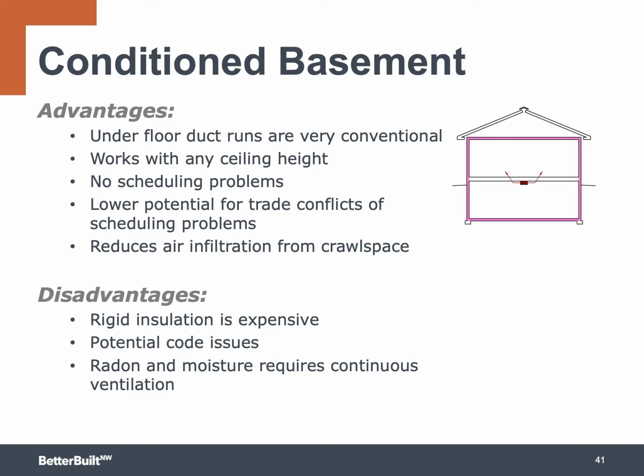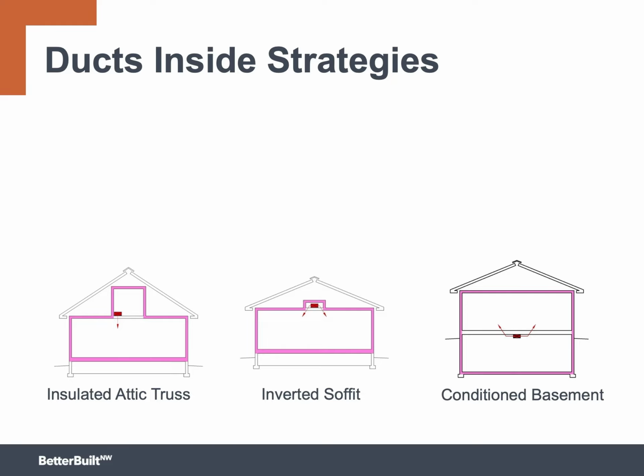If a basement is part of the plan, this is a great place to locate the air handler and the ducts for the ground floor. The entire basement can be included in the conditioned space, or maybe just a section. Either way, the walls must be fully insulated and sealed. If you're building in a high radon zone, then additional precautions are necessary. Inverted soffit, attic truss, and conditioned basement are covered in full detail on the ductsinside.org website.